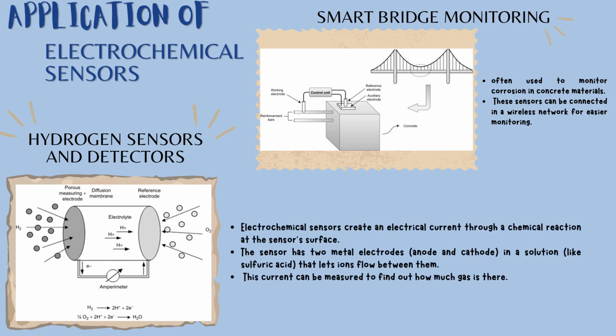The electrochemical sensors create an electrical current through a chemical reaction at the sensor surface. The sensor has two metal electrodes, anode and cathode, in a solution like sulfuric acid that lets ions flow between them. The electrodes are coated with a material like platinum to help the reaction happen. A membrane allows gases like hydrogen to pass through the sensor. The amount of current produced depends on the amount of gas, like hydrogen, present. This current can be measured to find out how much gas is there. Some sensors use a solid material instead of liquid to prevent leaks.